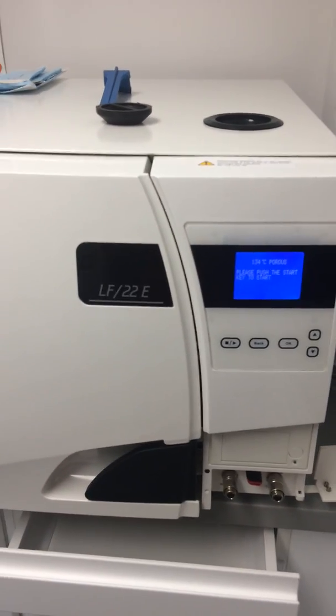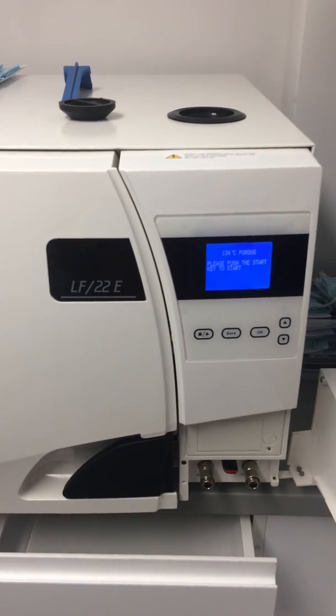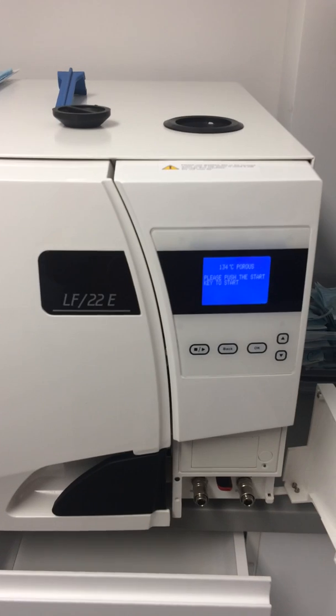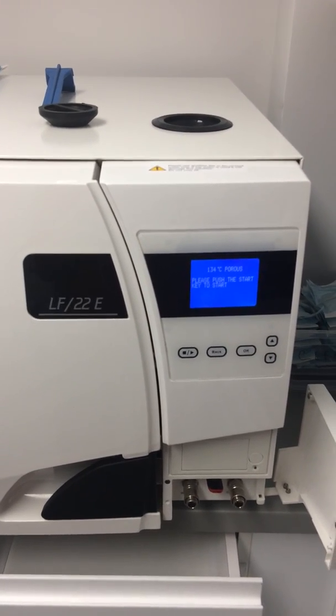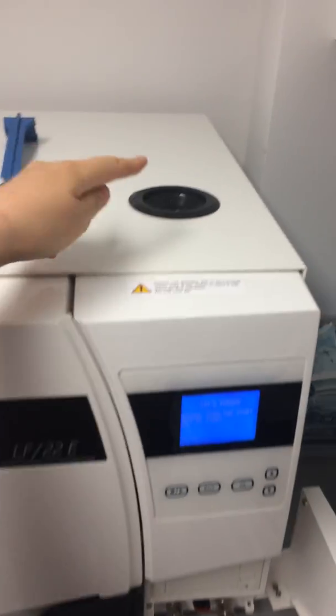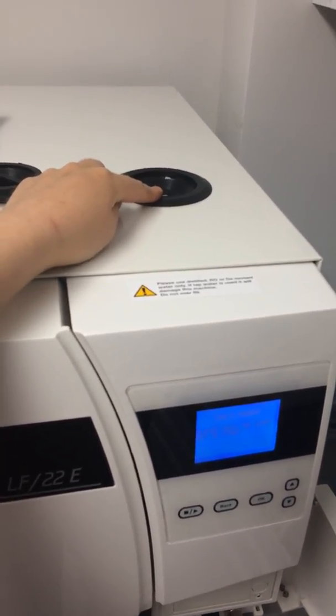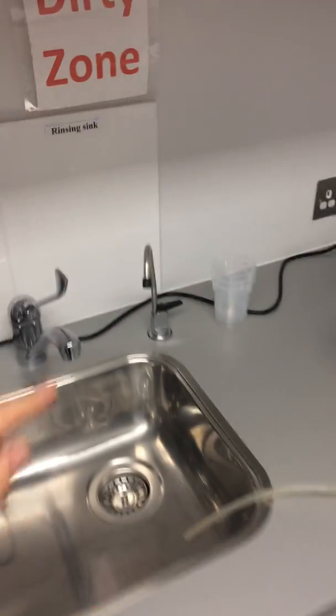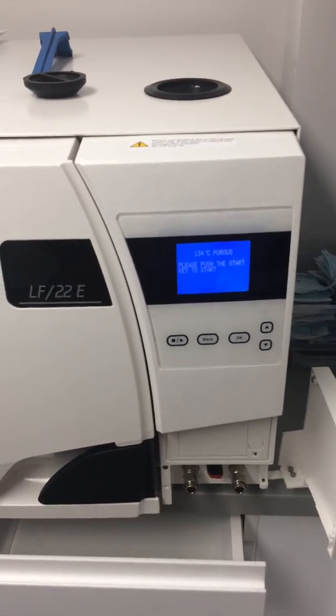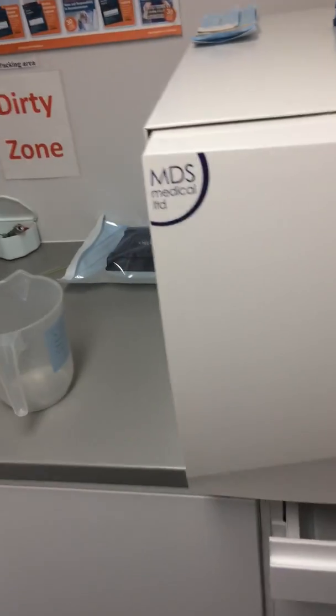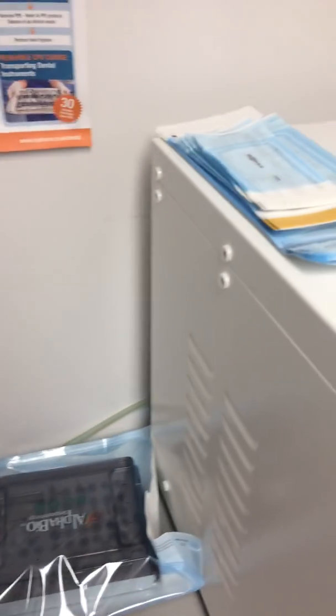Now I would like to explain what to do in case you have an error or the machine asks you to fill extra water or dispose of some. If the machine is asking you to fill the chamber with water, you just do the same as we did in the morning. You just pour extra RO water here. We have a special tap for RO, so you use this tap to do so. If the machine is asking you to dispose of used water, usually it does so automatically, but sometimes we need to help it a bit. As you can see here, we have a dispose water tube, and we just push it slightly to the front, and the machine will start disposing of water.